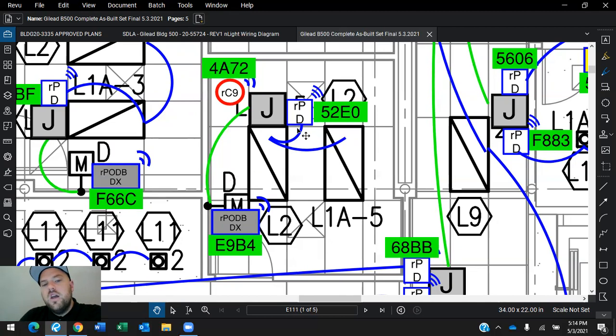When I come in the room, if this motion sensor is turned on, programmed and all set up, I'm going to walk in, the motion sensor detects my motion, and it tells this power pack to close the relay and allow the power side communication, the power from the 277 volt panel, to flow through the power pack, out this wire, into this fixture, and then into this fixture. Lights come on. Now, if I come over here to the wall and press the switch to turn it off, I'm overriding the motion sensor, and I am telling the power pack that it needs to open.